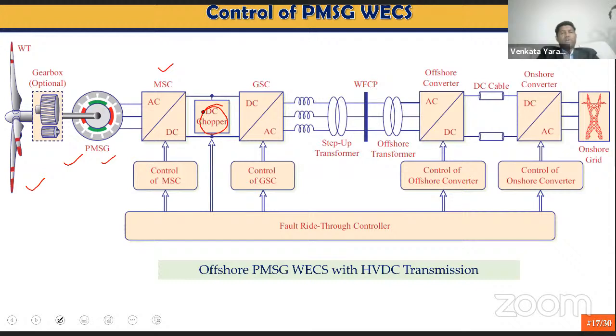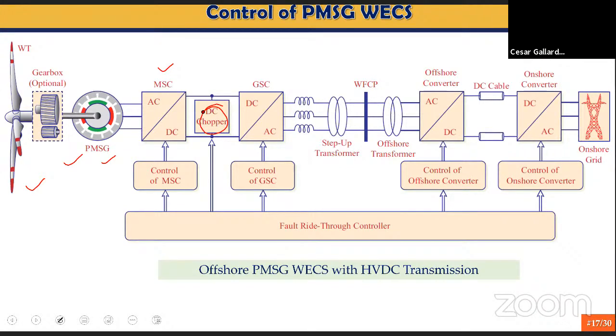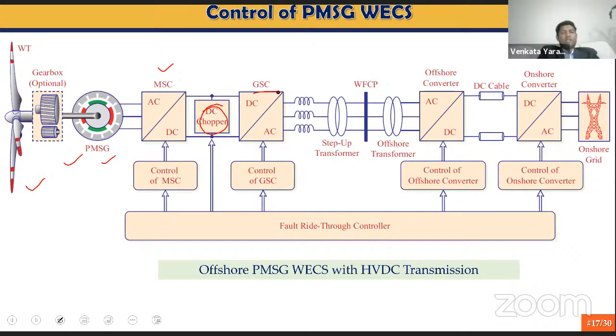If there is some fault, we need to inject only reactive power to the grid, and we need to limit the active power coming from the turbines. Whatever active power is already produced is going to be dissipated in the resistors. That is done through the DC choppers. And then we have the grid side converter, DC to AC conversion, and then a harmonic filter and step-up transformer.